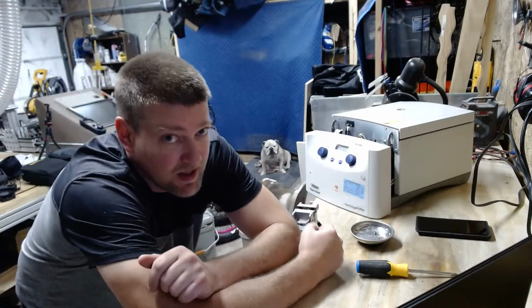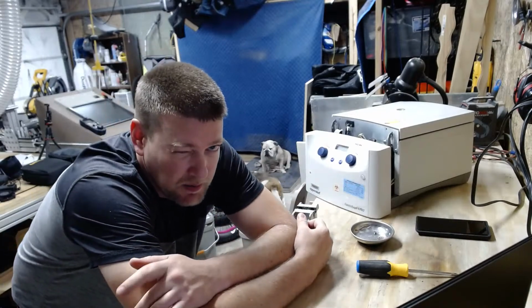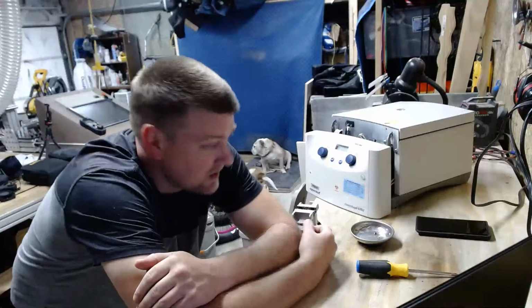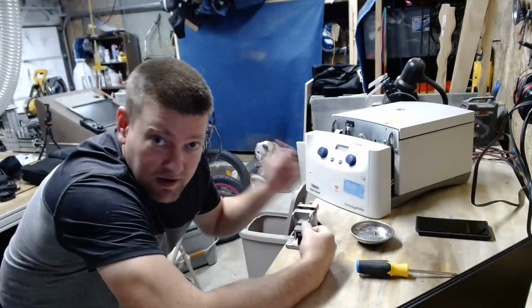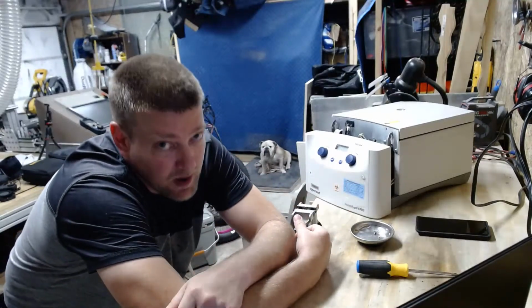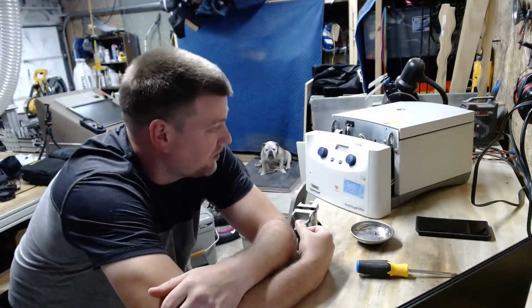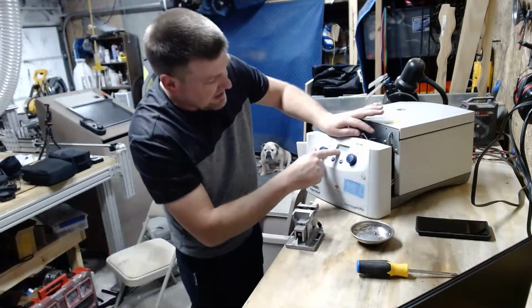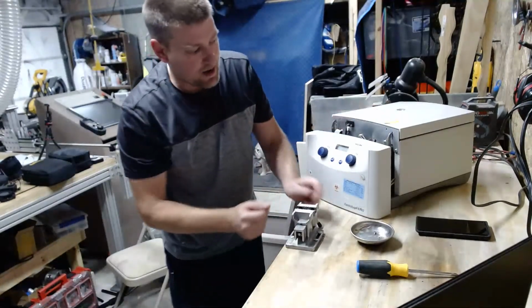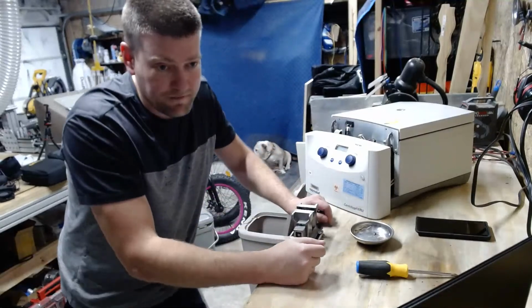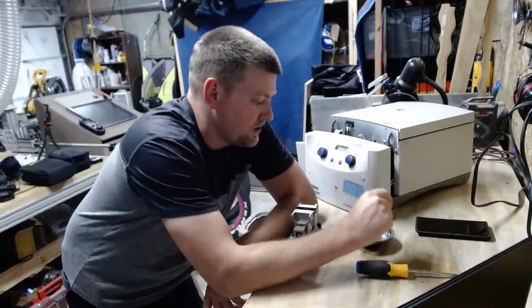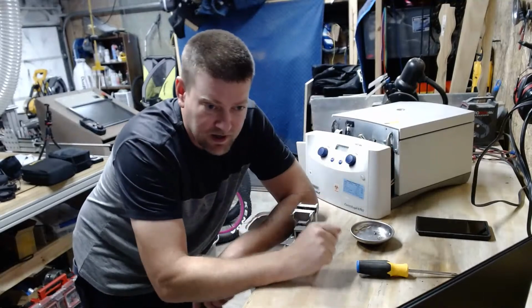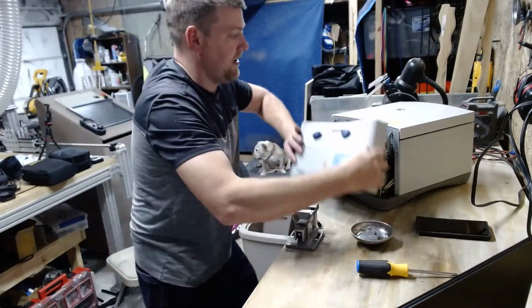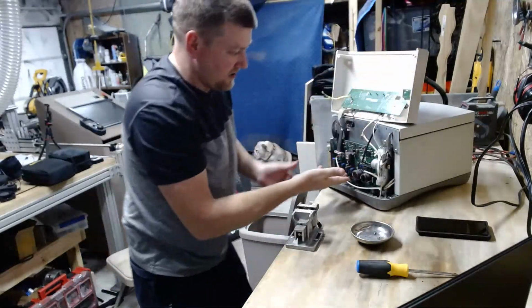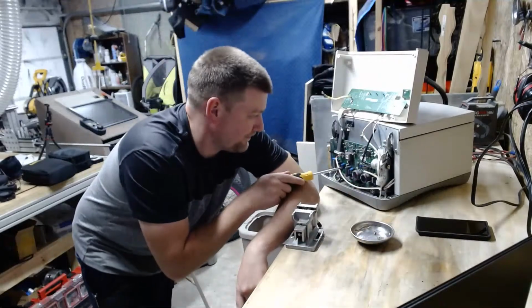So that's telling me the power supply is probably the issue, because if this guy's flashing, that means I definitely have AC power. It's probably the DC side that's got a problem, because the display right here being lit up, that's all off your DC power bus. So you've got the AC comes in, it gets converted to DC in your power supply, which you can see right here.